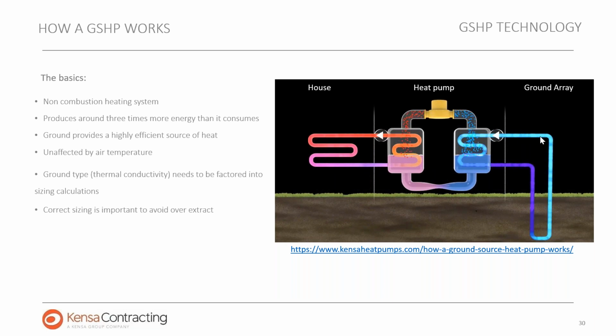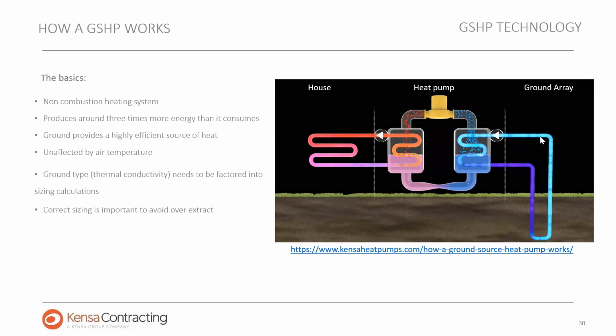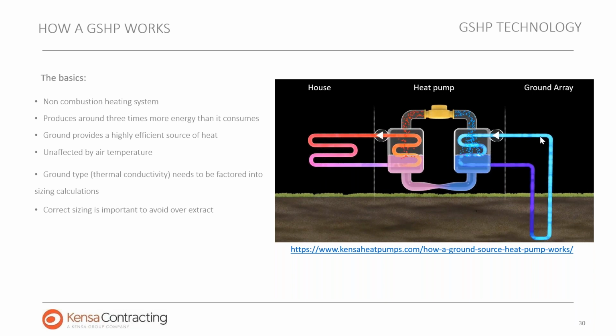That gas is then passed to a compressor at the top of the heat pump, that yellow system that you can see going up and down. That compresses that heat and supercharges that gas temperature from 10 degrees centigrade up to 65 degrees centigrade. That hot gas is then passed to the left-hand side of the heat pump, the red part there, to a secondary heat exchanger. So we're now exchanging that heat from the gas into our heating system and our domestic hot water supply.